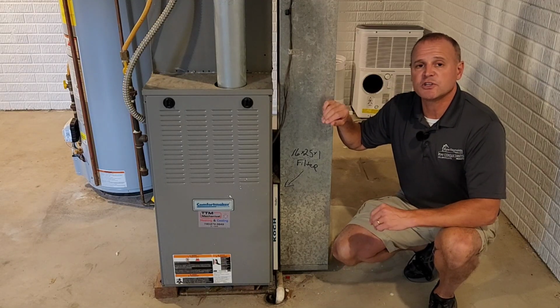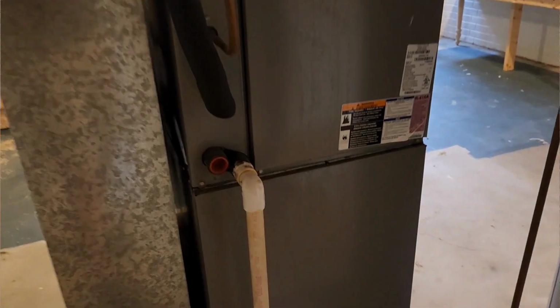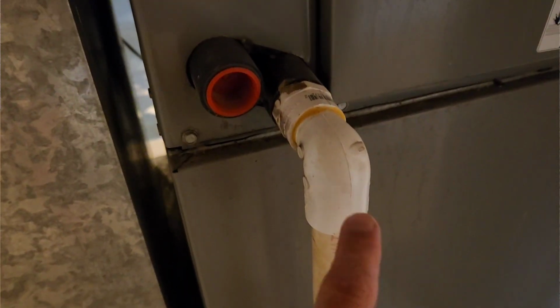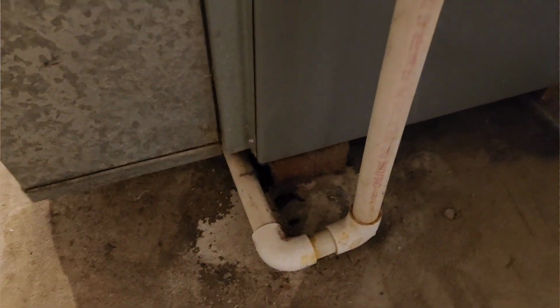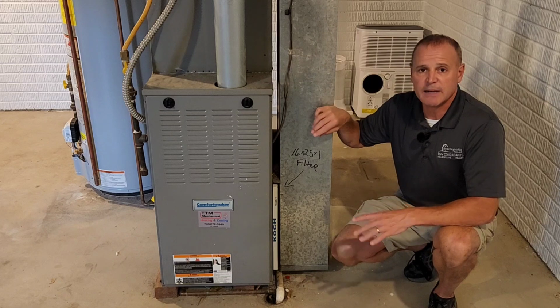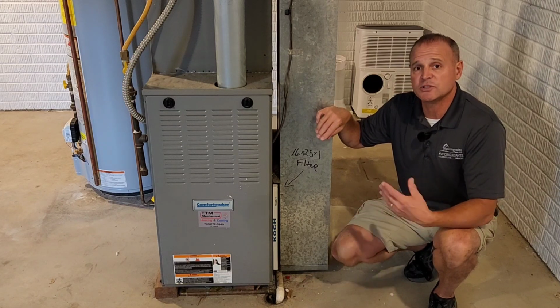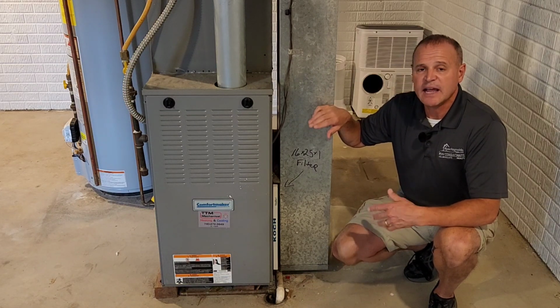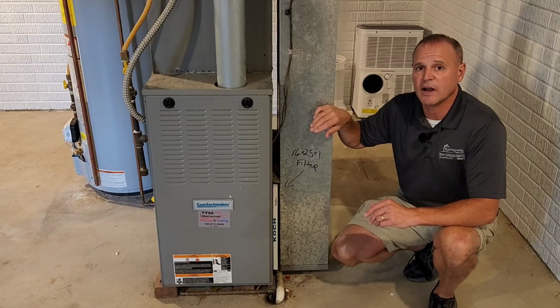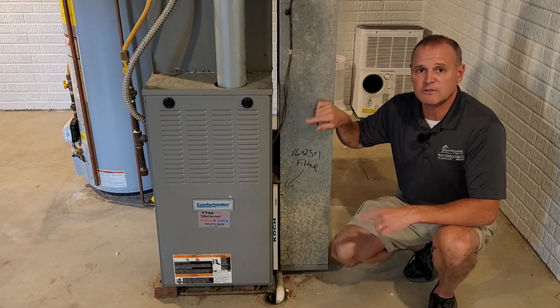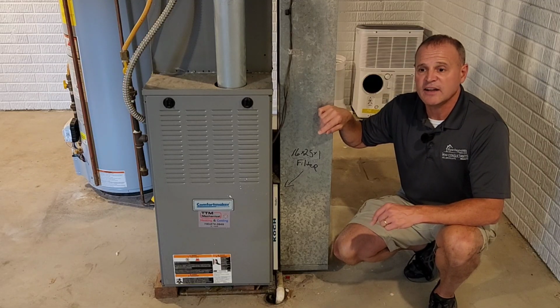In most furnaces, you're going to have this white PVC line. It's a 1-inch line coming out, and it'll connect to a T. In this case, it connects to an elbow, and then it goes down and curls around underneath the furnace and goes into the floor drain there. Sometimes it won't go into a floor drain, but into a condensate pump, and then it'll be pumped into a drain somewhere else. Either way, the water needs to get through that condensate line down to the floor drain.